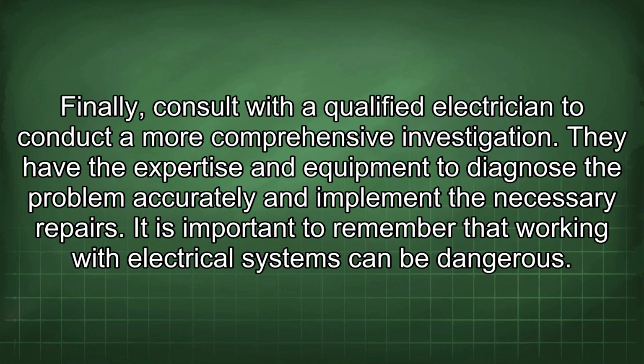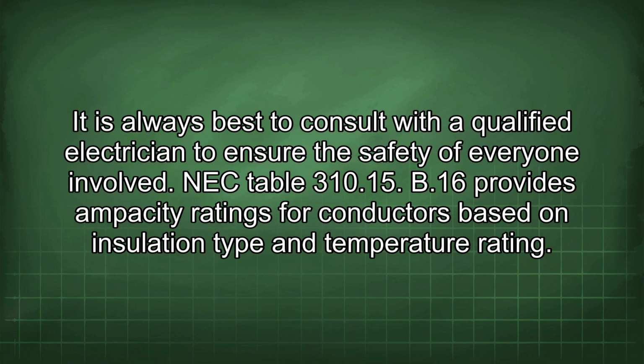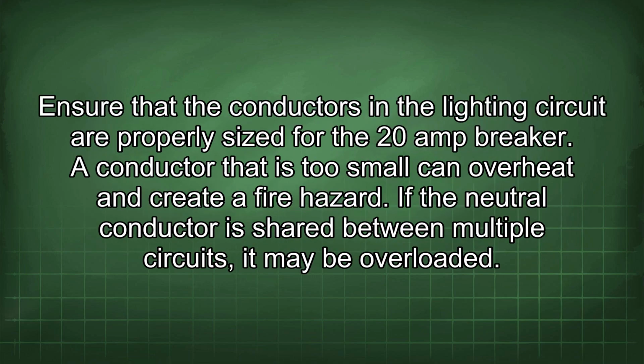Finally, consult with a qualified electrician to conduct a more comprehensive investigation. They have the expertise and equipment to diagnose the problem accurately and implement the necessary repairs. It is important to remember that working with electrical systems can be dangerous. It is always best to consult with a qualified electrician to ensure the safety of everyone involved. NEC Table 310.15(B)(16) provides ampacity ratings for conductors based on insulation type and temperature rating. Ensure that the conductors in the lighting circuit are properly sized for the 20-amp breaker. A conductor that is too small can overheat and create a fire hazard.